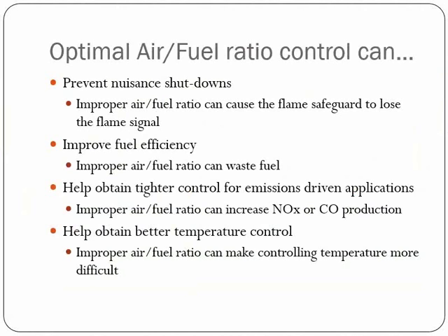The majority of combustion processes, ovens, furnaces, dryers, in an effort to maintain temperature will increase or decrease firing rate. There are some other applications that are either on-off or high-low. They also utilize air-fuel ratio in their own ways, but for today's purposes, I'm going to talk a little bit more about dynamic systems where we're controlling and throttling the firing rate up and down and how the air-fuel ratio control maintains that ratio during the separate firing rates.